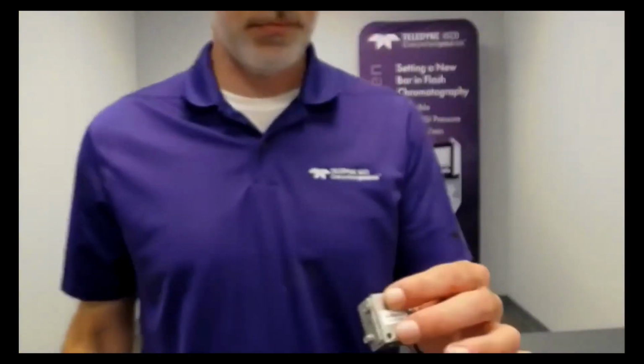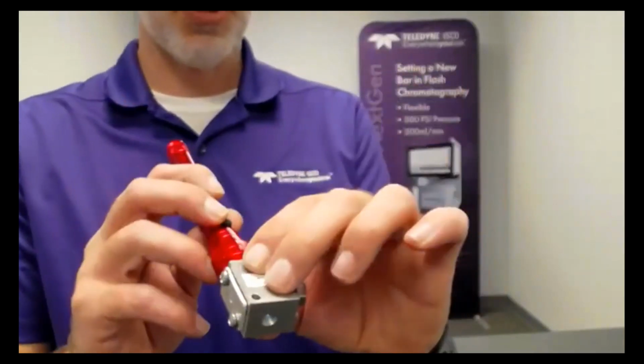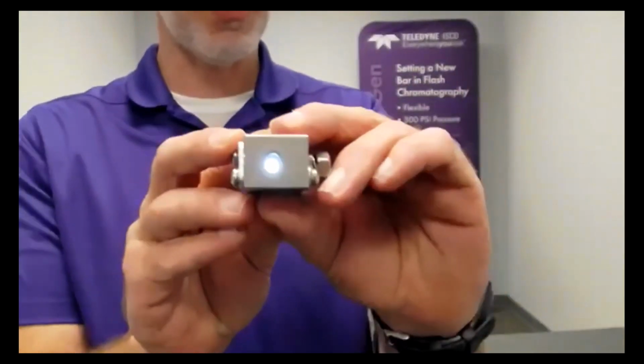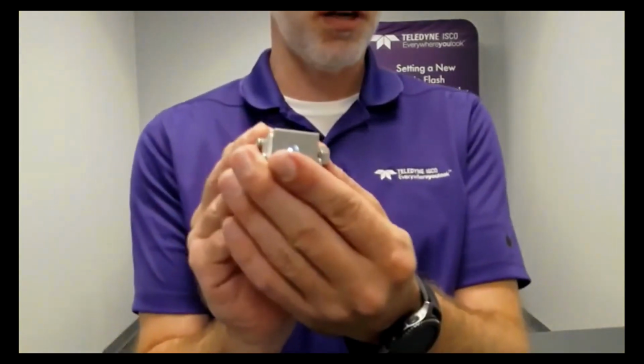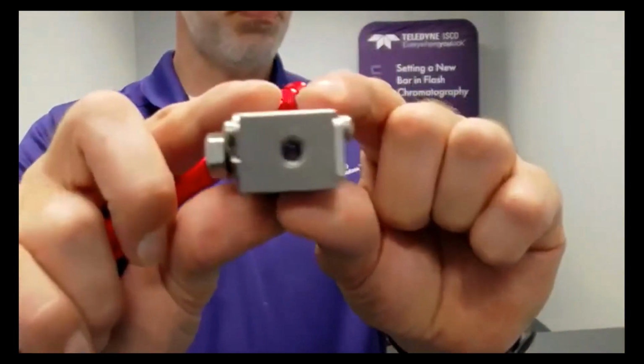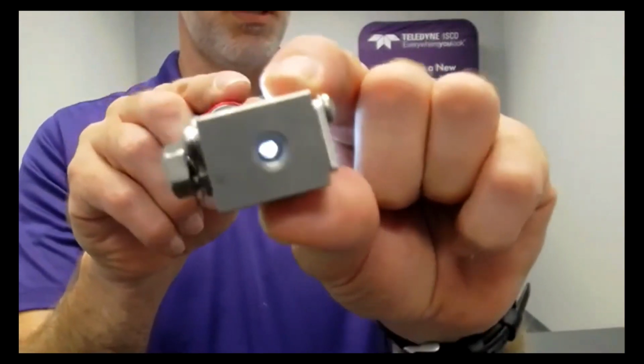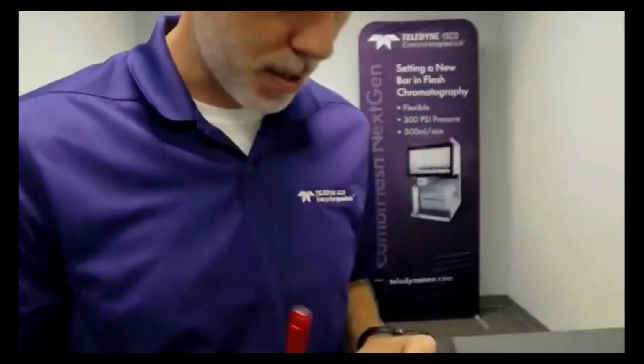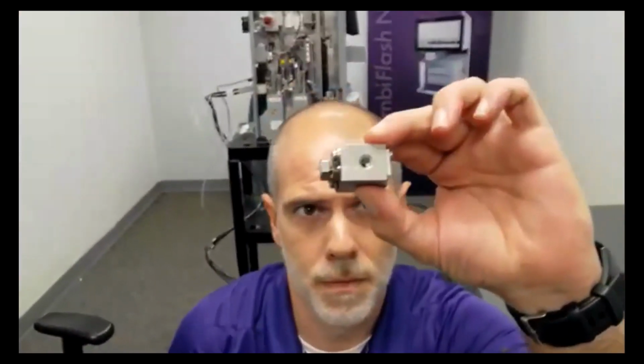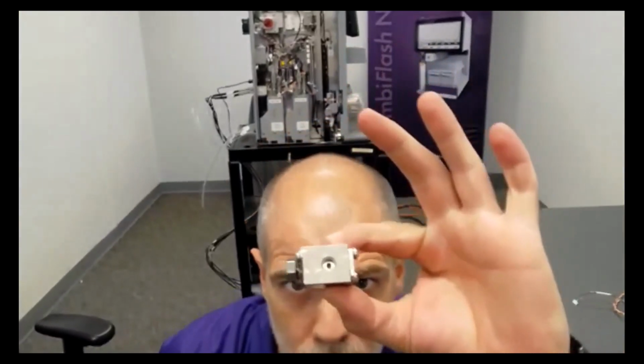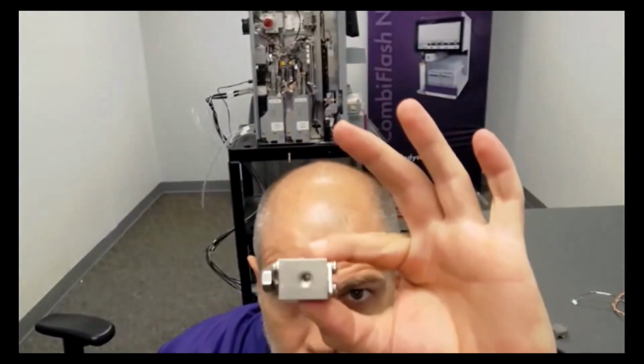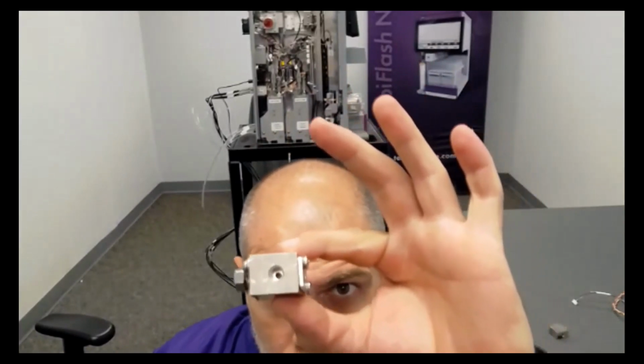So when you take out a flow cell, you're going to have a gap in there. So what I like to do, I like to shine a flashlight through. You really can't see through there. But you shine a flashlight through because you want to see any imperfections that are in there. Now, a lot of times you can just blow that out and you'll be able to see that gap in there. Now, if you need to, you just hold it up to a light, like I'm doing. You can't see the light, but I'm holding it up to a light and this gap has closed on this one that I'm holding.